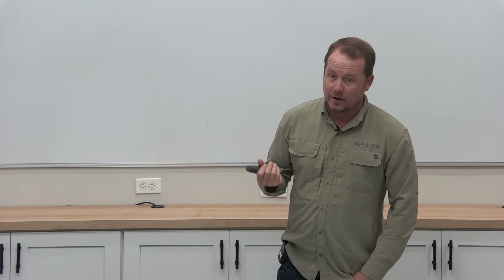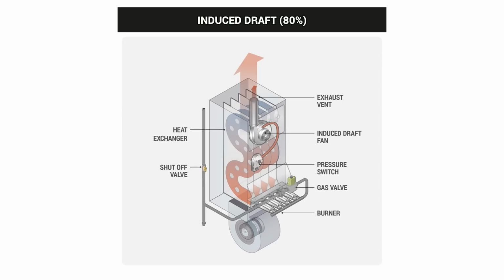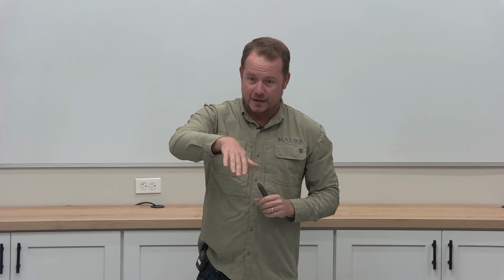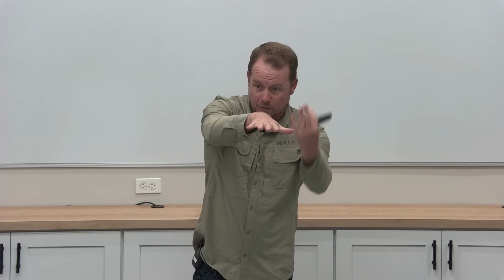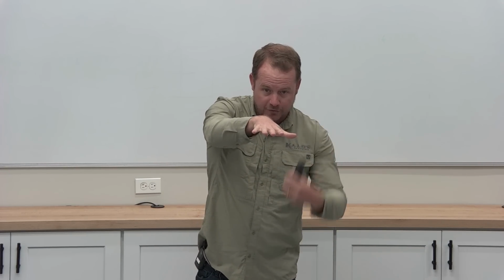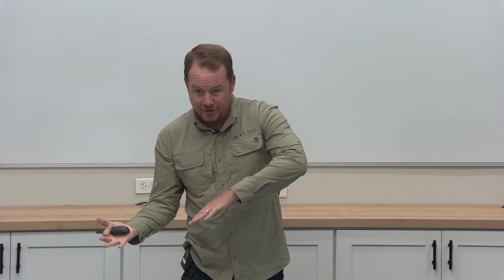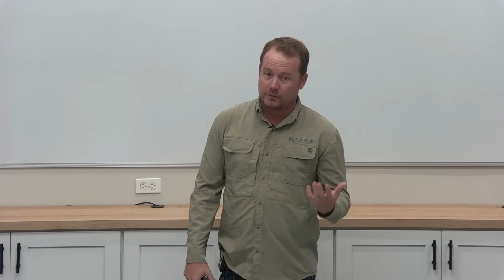What else? Another one is when you run a gas furnace, especially in our market, because we have these 80% furnaces. In an 80% furnace, you have the burner assembly up top, right? And you can watch the flames, and then down below, you have the cover and the blower and all that. That should be covered whenever you operate. Otherwise they don't work right, because you have air sucking in. You have to have that covered, and you should watch the flame when it first starts up. The flame goes first, and then the blower starts. If the flame goes first, the blower starts, and all of a sudden the flame starts changing on you, that's an indication that you're mixing the air side, the blower side, with the air that's entering the furnace for combustion. So that's another really big factor.